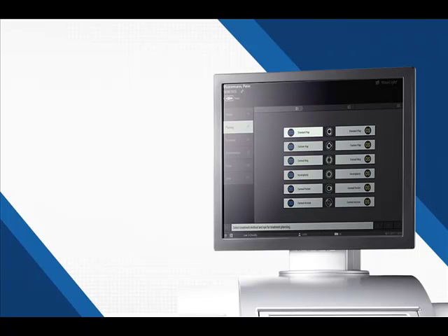The overall increase in pressure in the eye is 16 millimeters of mercury. So this means if the patient has a pressure of 10 during the procedure, their pressure will go up to 26. If the patient has a pressure of 20, it will go up to 36 during this procedure. LensX's increase in pressure is so low, it is approved to be used with patients who have glaucoma.